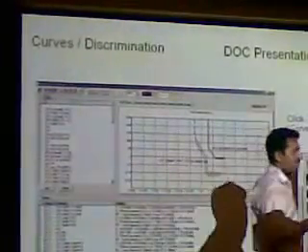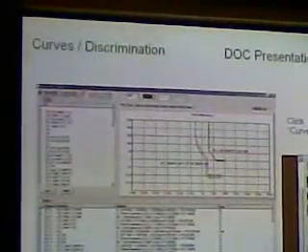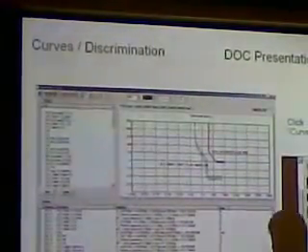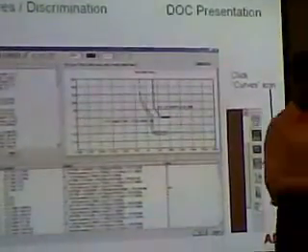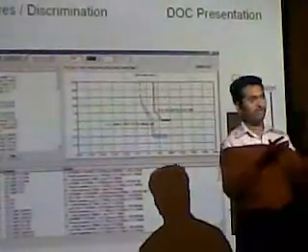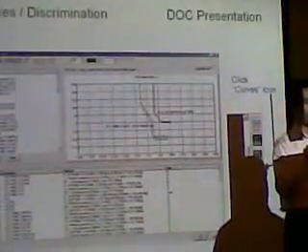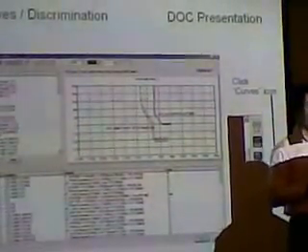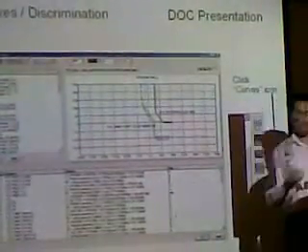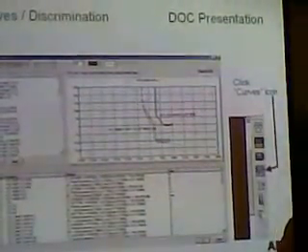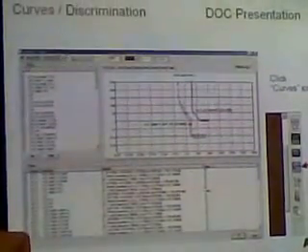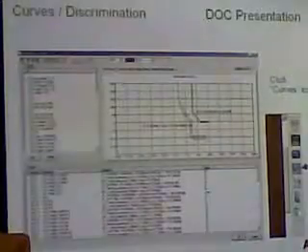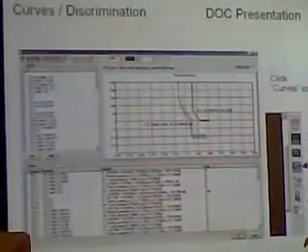Then we will have to look at that. But it's not our duty, because the contractor has selected the cable size and the breaker size, everything. But the main thing is to calculate the short circuit level, to justify that the breaker provided is sufficient for the network. Right? But as additional information, suppose if we have good relations, this can be informed to the contractor: this is not protected, take care. Maybe you will have to increase the cable size and the breaker size. This additional information, when a problem comes, you can retrieve it.